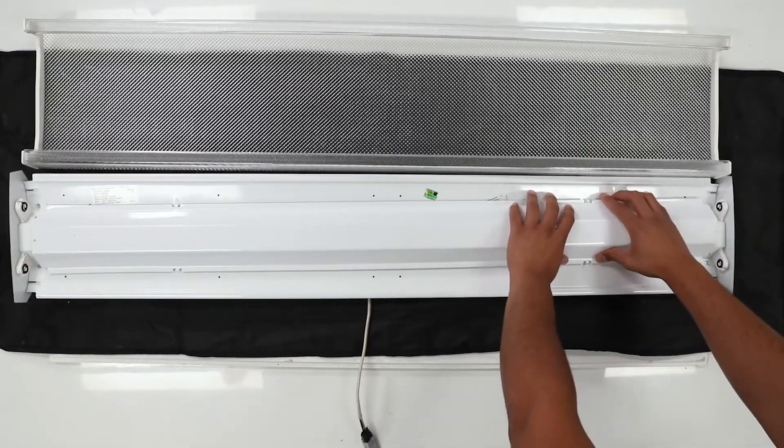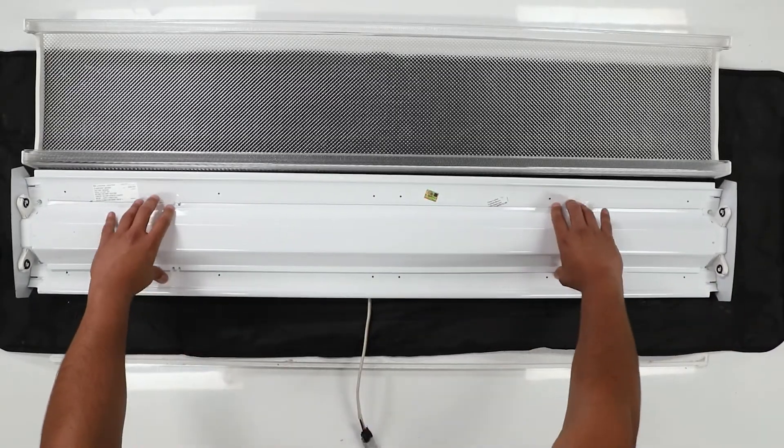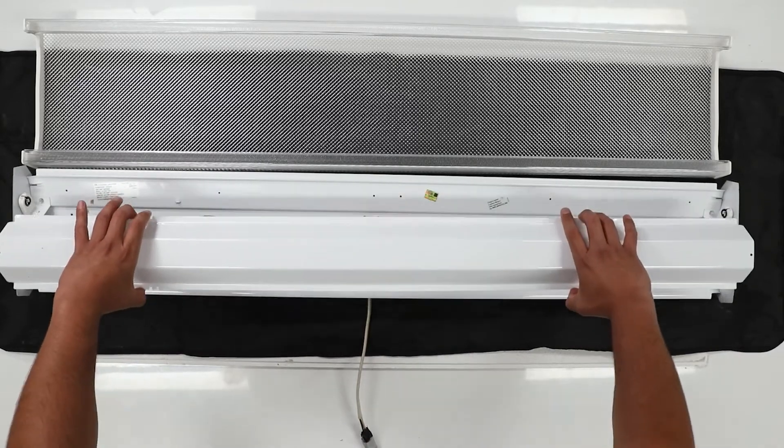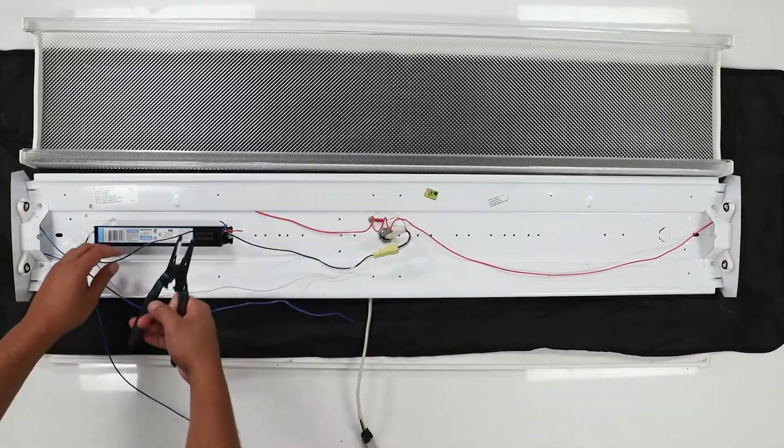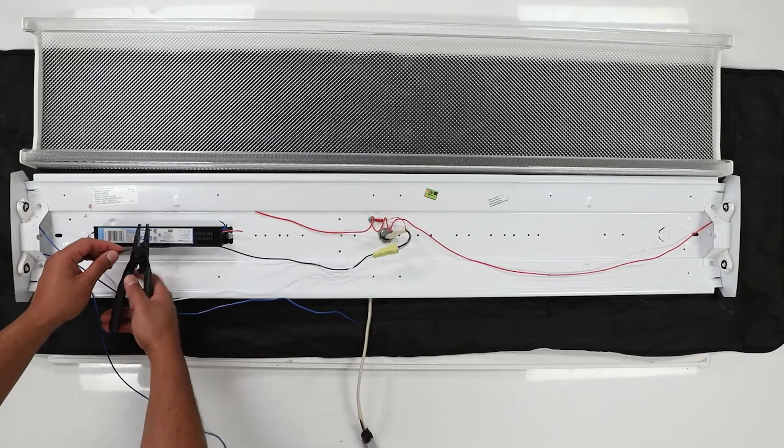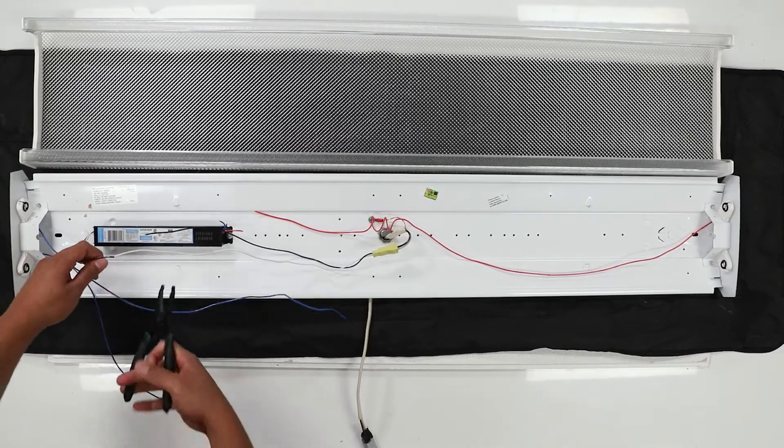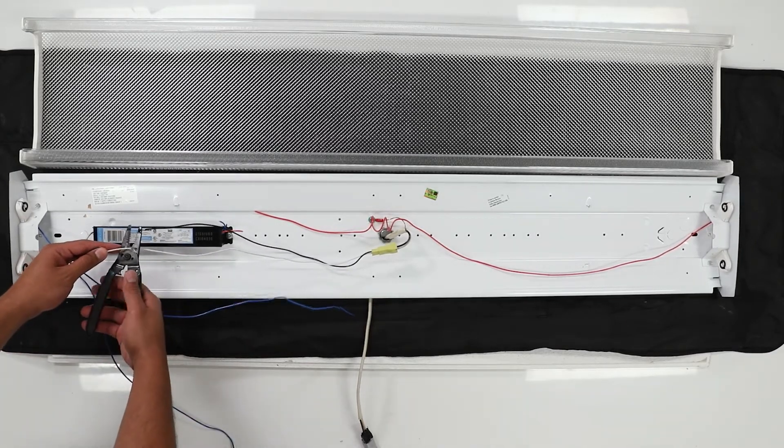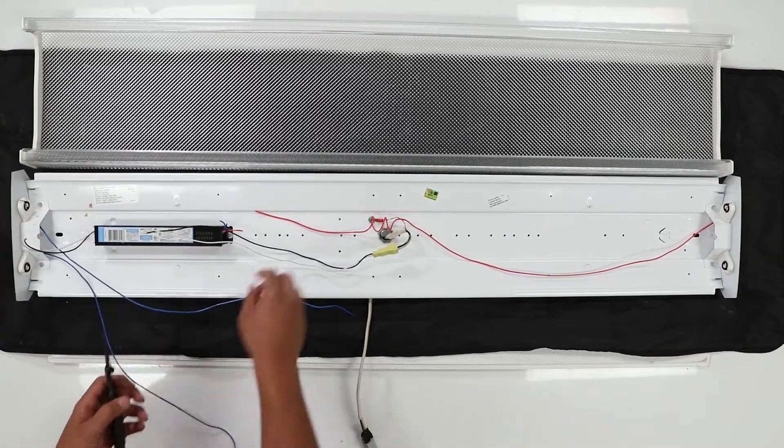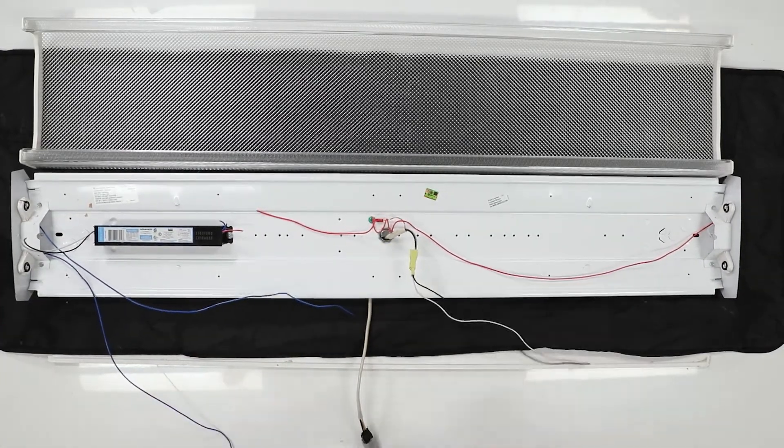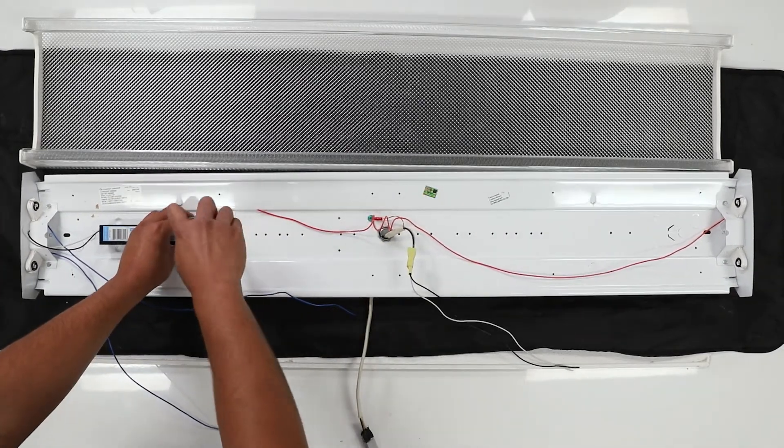Remove the ballast cover to expose the wiring. First, disconnect the hot, neutral, and ground wires that are connected to the ballast. Then, cut all the wires leading from the ballast to the lamp sockets. Be sure to cut them close to the ballast so that you have extra wire to work with later on.